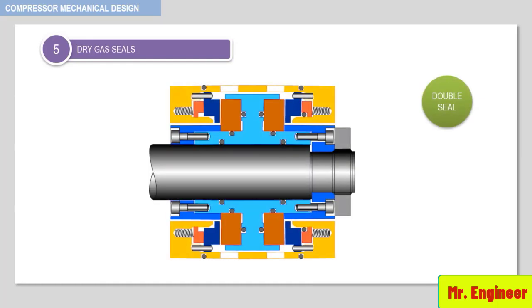A double arrangement is a sealing system which reliably prevents product gas from escaping to the atmosphere. It involves feeding a buffer gas between the seals at a higher pressure than the product pressure. Part of the buffer gas leakage escapes to the atmosphere side and the other part to the product. Typical applications are found mainly in the petrochemical and refining industries.